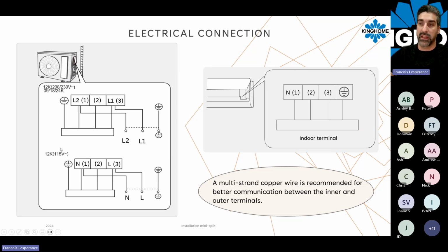That will be the same thing if you're working on a 120-volt system. Terminal 2 and terminal 1 are still your communication cable. You have to unplug the wire and, just with your multimeter, measure on the terminals to see if you have 56 volts.